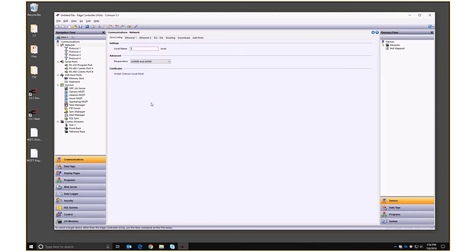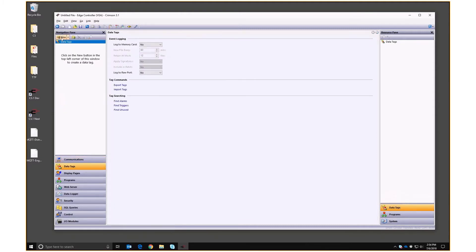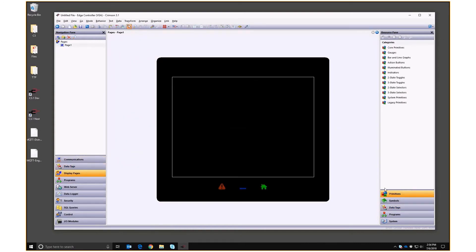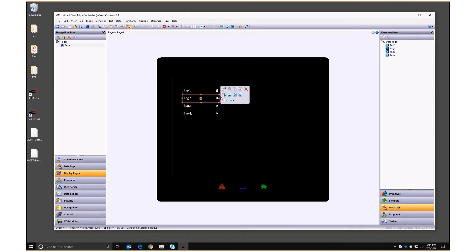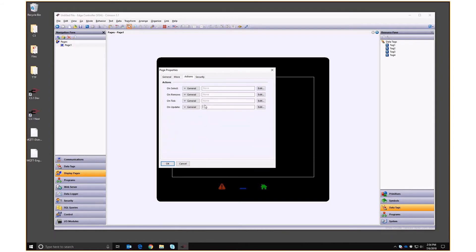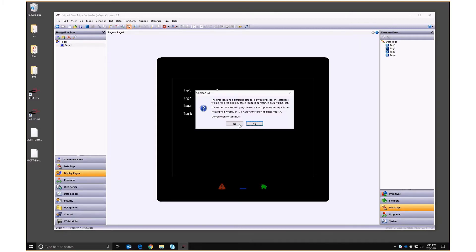Let's open Crimson and set up a database. I'm using an edge controller and I'll give it a local name. I go into tags and create four numeric tags, bring them onto a page, set them all to data entry. Then in the page properties under actions on update, I'm going to increment tags two, three, and four. Now I'm going to download that to my device.